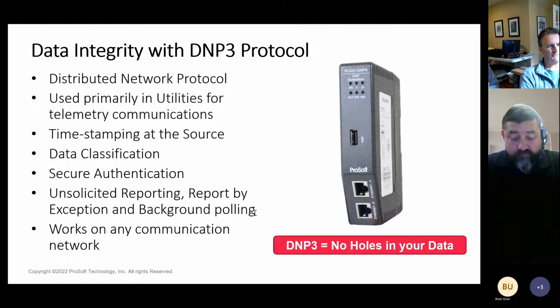If you're considering the role of PLC data specific to compliance for both freshwater and wastewater regulatory and operational reporting, it's first important to ensure you have no holes in your data. DNP3 ensures this by time stamping events with a clock synced by the master at the SCADA system, and by logging events locally in an uncompromised payload before sending that data to the master at your specified poll rate. In parallel, there's extreme efficiency with the prioritization of this data. There are four data classifications to ensure the most critical data, like alarming, gets out in real time, while everything else is timestamped, logged, and only sent out at your poll rate.